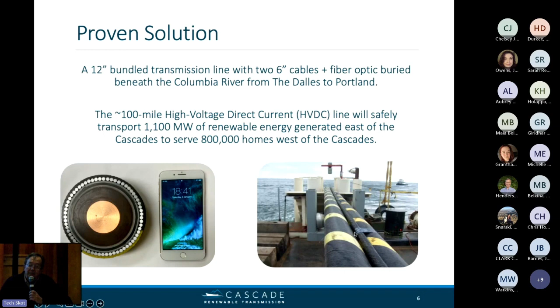So what you see for the cable, that's basically delivered into the river the same way. I've got a slide later that explains how we actually install it in the river bottom. As a practical matter, once it goes in - our Neptune project is in its 17th year, our Hudson project is in its 10th year - the cable systems are fairly benign and quiet, they just operate. And it's not because they're not stressed: that cable on the left-hand picture is 500,000 volts, 24/7, 365, year in and year out.